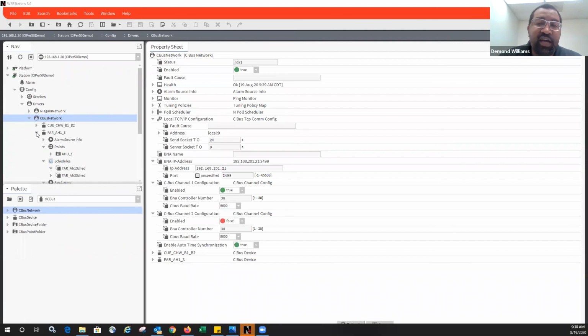The same thing for the XL500 that has the multiple card slots and you can just keep adding hardware onto it. It's only going to count that one CPU out of that device as one device, but I could have up to 5 different air handling units on there. So one of the things also is you can put this device on the Honeywell network while the Honeywell EBI or the older XBSI network is still online, and you can actually build your system at the same time so you don't interrupt or take the customer offline or anything like that.